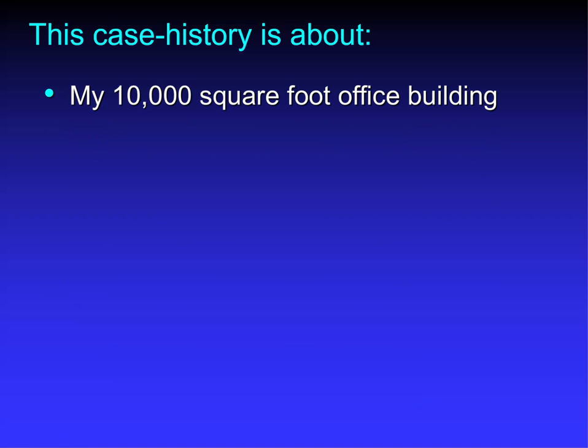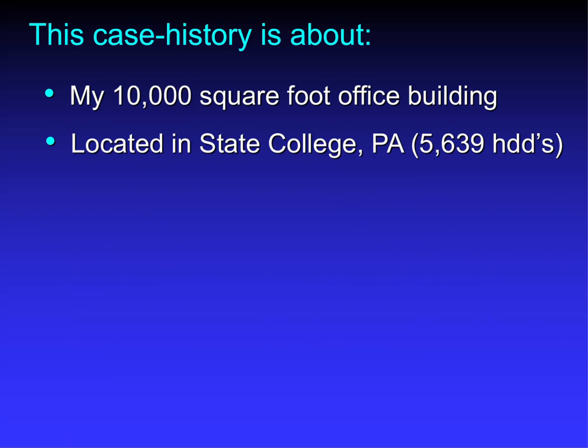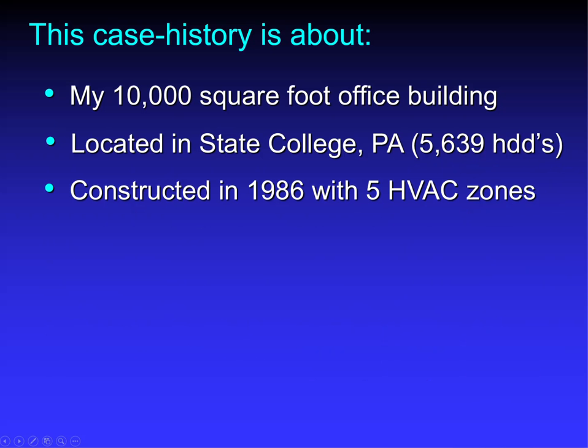This case history is about my 10,000 square foot office building heating and cooling system, and it's located in State College, where the winter temperatures require 5,639 heating degree days. My building was constructed in 1986, and it has 5 heating, ventilating, and air conditioning zones.